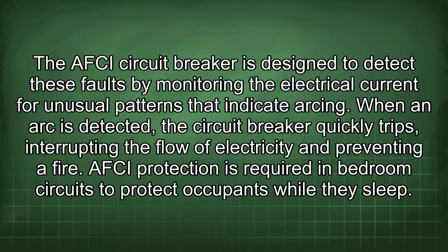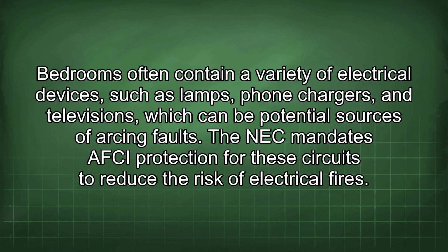The AFCI circuit breaker is designed to detect these faults by monitoring the electrical current for unusual patterns that indicate arcing. When an arc is detected, the circuit breaker quickly trips, interrupting the flow of electricity and preventing a fire. AFCI protection is required in bedroom circuits to protect occupants while they sleep. Bedrooms often contain a variety of electrical devices, such as lamps, phone chargers, and televisions, which can be potential sources of arcing faults. The NEC mandates AFCI protection for these circuits to reduce the risk of electrical fires.